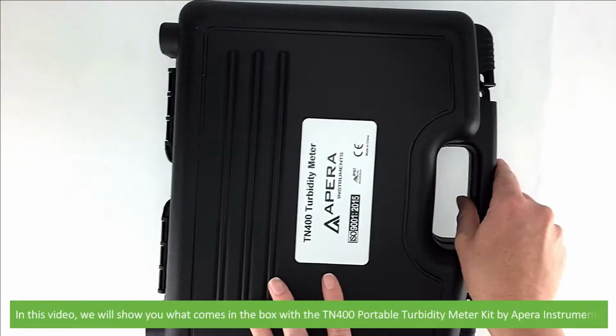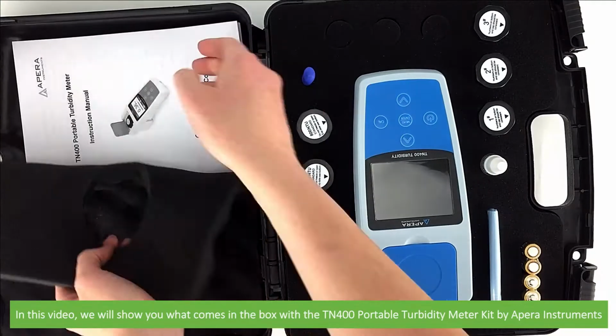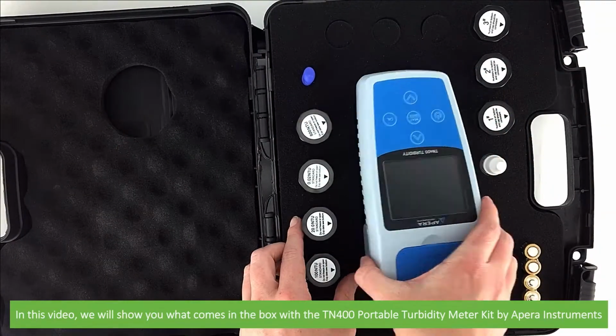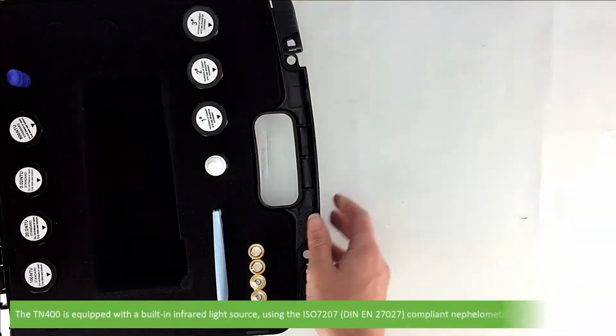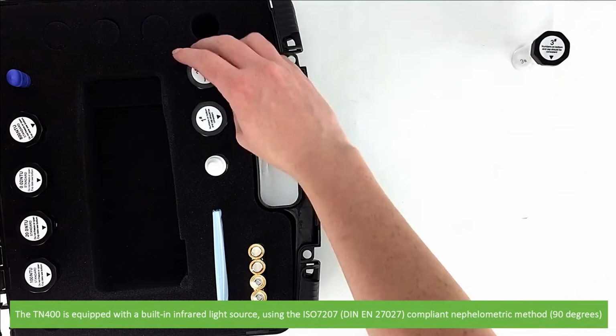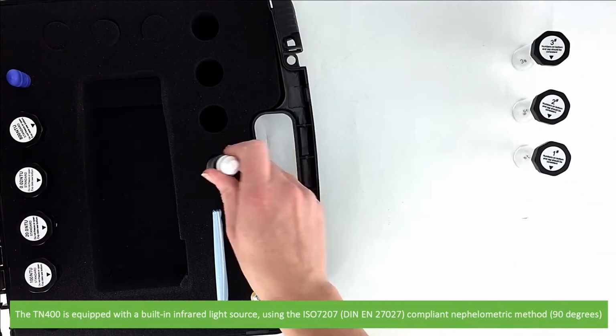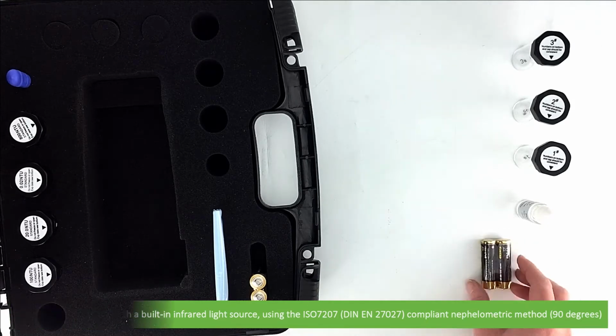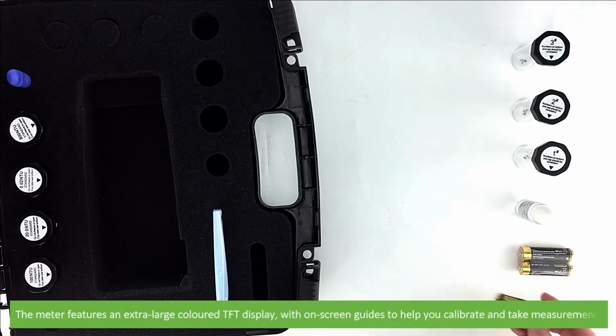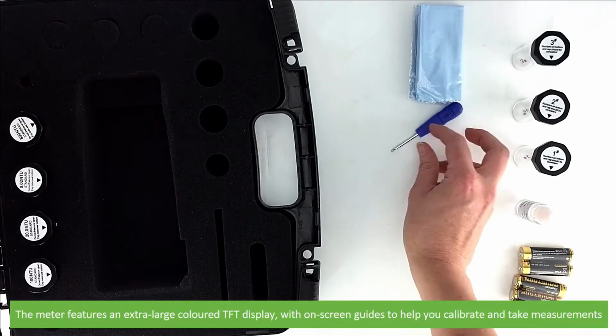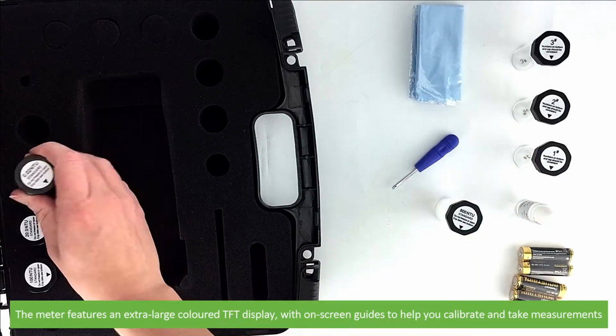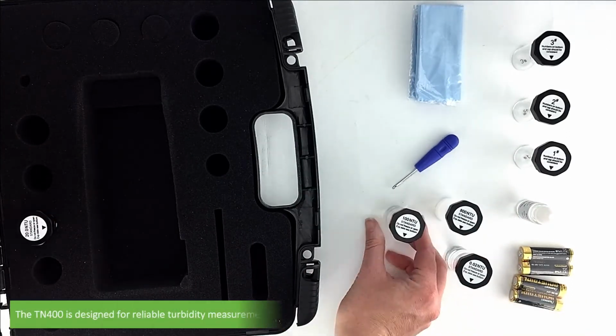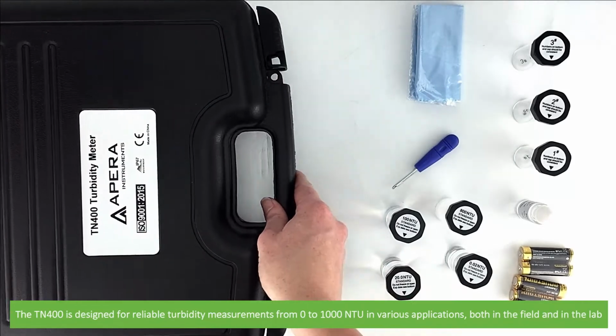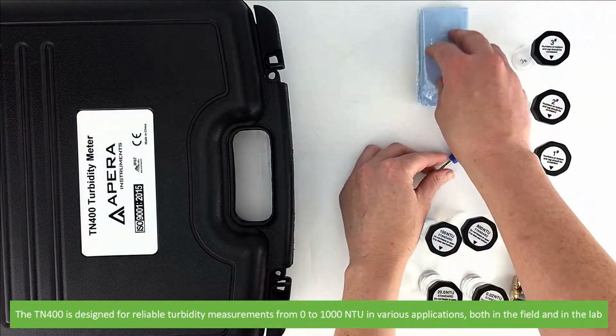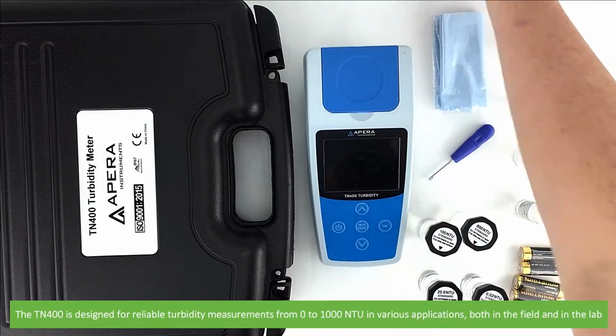In this video we'll show you what comes in the box with the TN400 Portable Turbidity Meter kit by Apera Instruments. The TN400 is equipped with a built-in infrared light source using ISO 7207 compliant nephelometric method. The meter features an extra large coloured TFT display with on-screen guides to help you calibrate and take measurements. The TN400 is designed for reliable turbidity measurements from 0 to 1000 NTU in various applications, both in the field or in the lab.